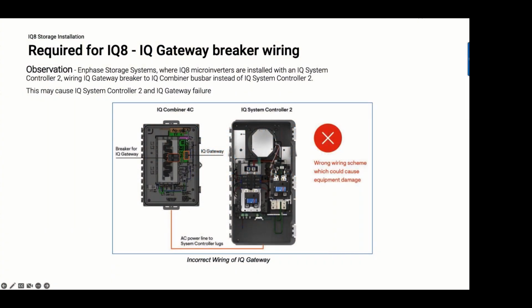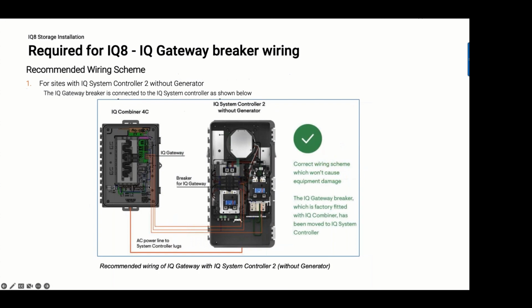The picture shown here is how the IQ gateway is typically powered from the breaker on the combiner bus directly to the IQ gateway. This is a wrong wiring configuration when using IQ8 microinverters. For correct wiring, the IQ gateway can't be powered from the IQ combiner. It has to be powered directly from the common bus in the IQ system controller. There are a few ways to do this. Pictured here is one approved method to do this.